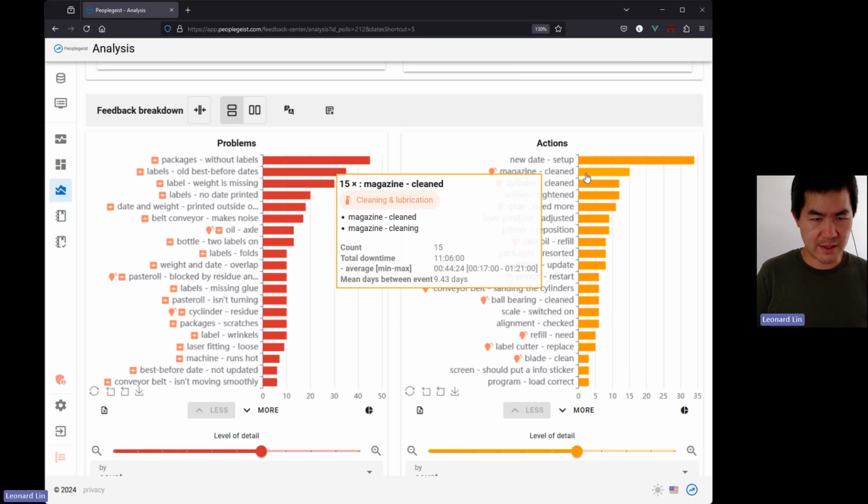In total, the software understands and will point out 4 classes of preventive actions. One is cleaning and lubrication. Then the other one's with consumables, so for example, filter change, refill oil, cooling agent. Then we have wear and tear, replacement of parts, how to schedule inspections, and also calibrations and alignment. So when frequent calibrations happen, is it something that can be done in a scheduled manner or not?